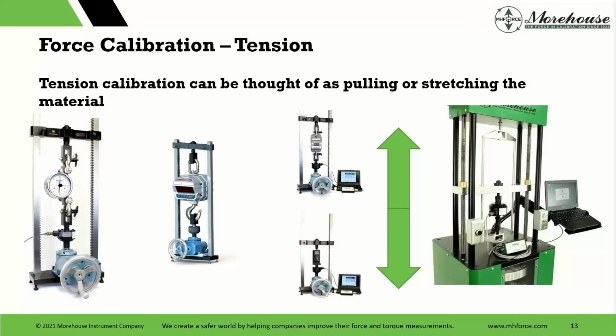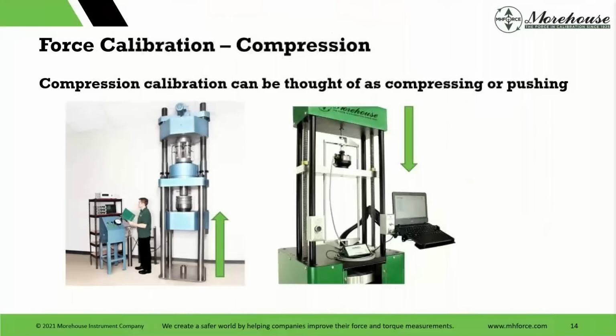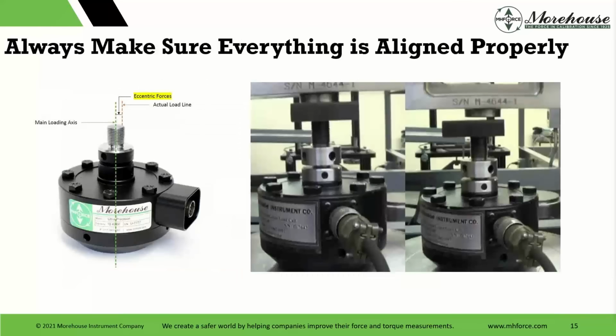Force calibration, here's tension, right? We were talking compression, tension. A compression is a push, tension is a pull or stretching. So that gauge was being pulled when actually it was designed as a push gauge. So talking about safety, one thing we really want to do when we're making force measurements, just for good force measurements, good repeatability, reproducibility, is we want to make sure everything is always aligned properly. This video here, picture, it's a video that's online, shows a Morehouse load cell. One picture you can see a nice vertical line of force on the machine, and then on this side just not aligned well at all.